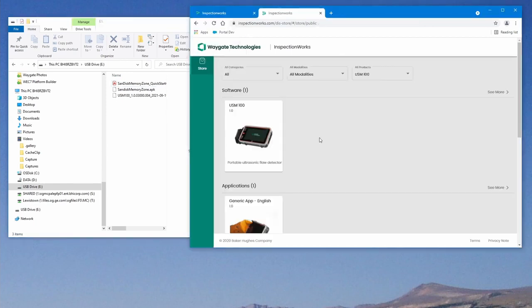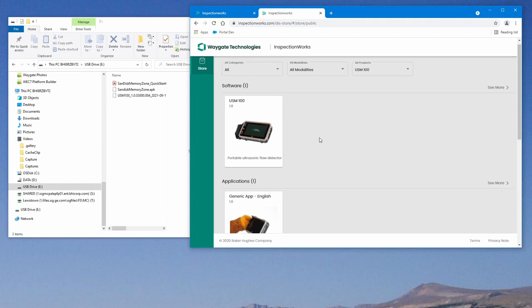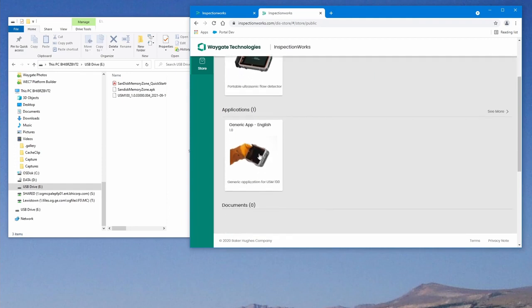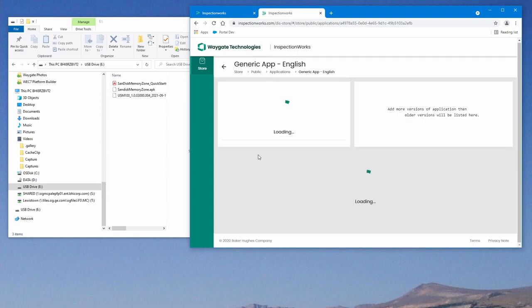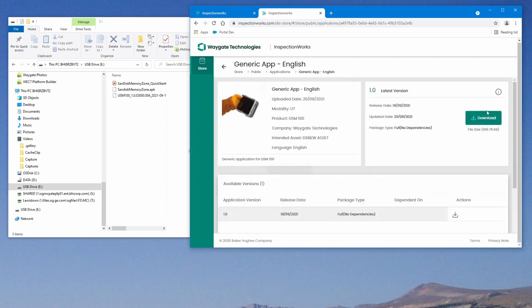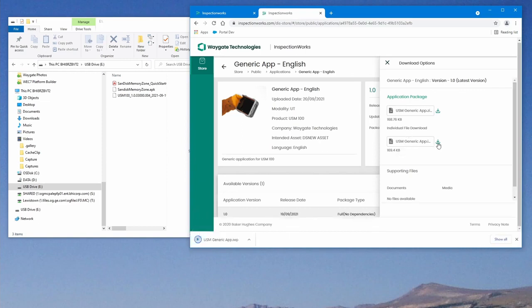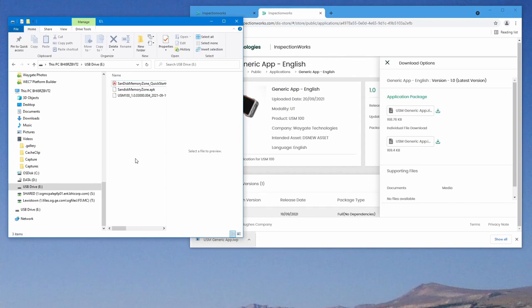Okay, we've come back to our main page for the USM 100. We're going to select the generic app. We're going to select download. And we're going to select download the individual file. And we see our app has downloaded. And we'll copy that over to the memory stick.